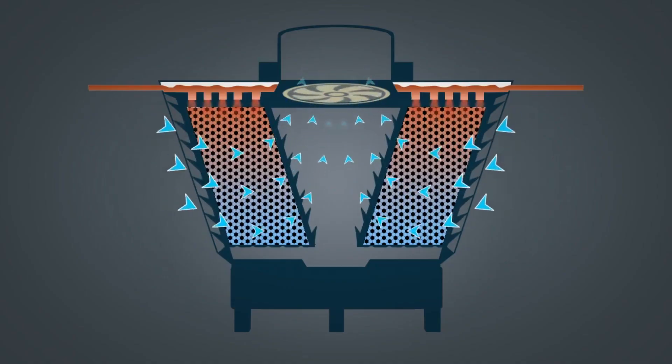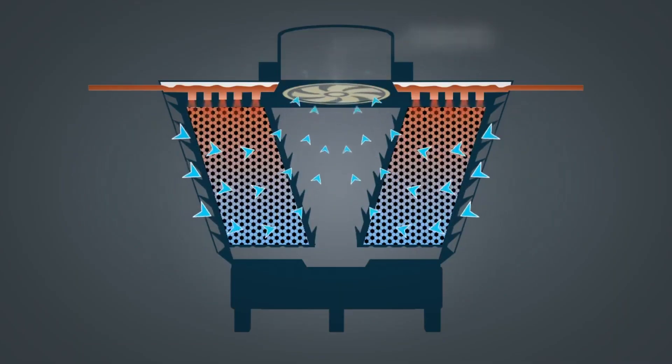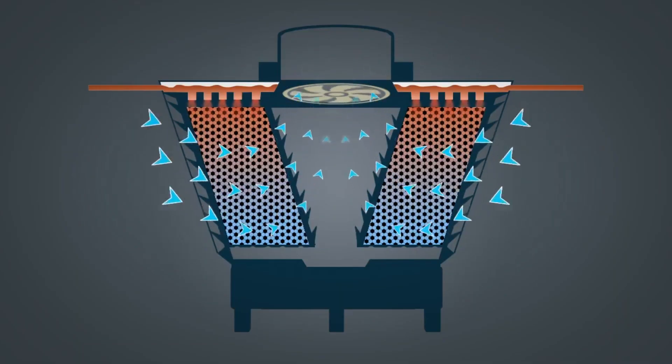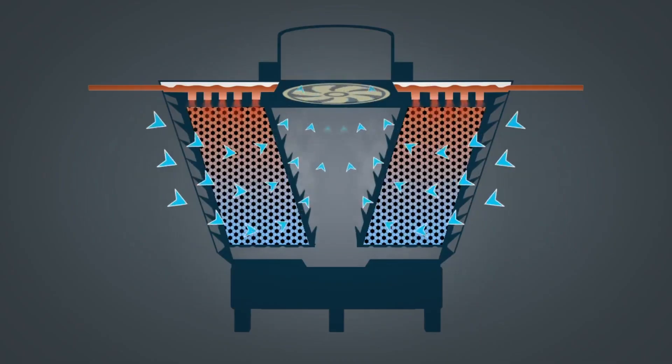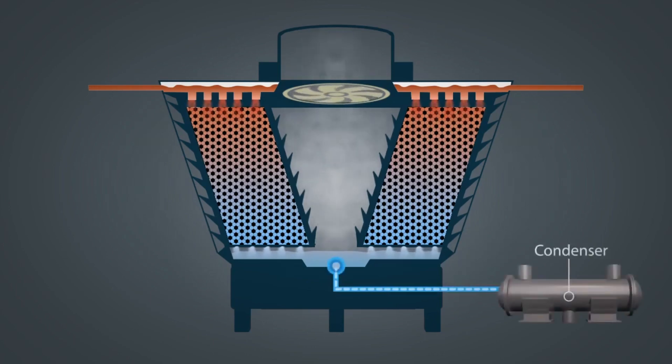The exhaust fan installed at the top draws air across the water droplets and cooling by exchange of latent heat results in the form of evaporation of a small amount of water. After passing through the fill media, the water gets collected in the basin. From the basin, it is pumped back to the chiller condenser section by the condenser water pump.